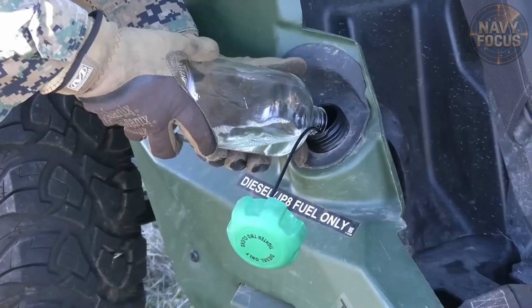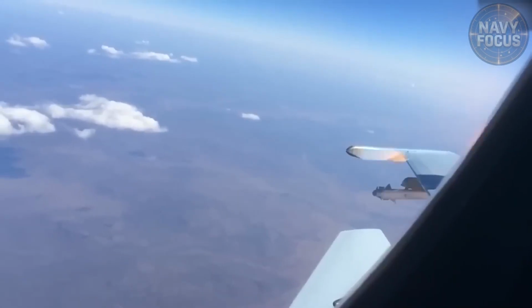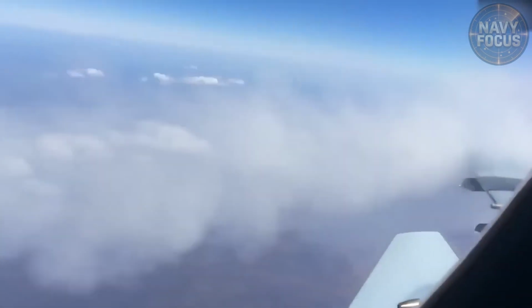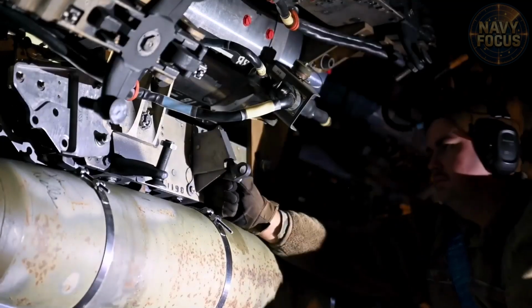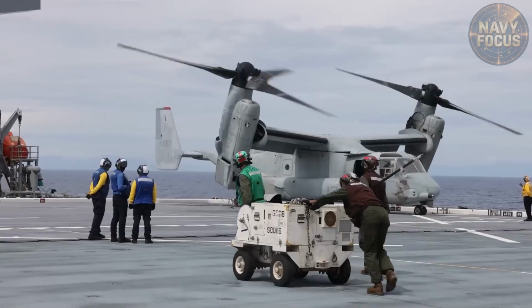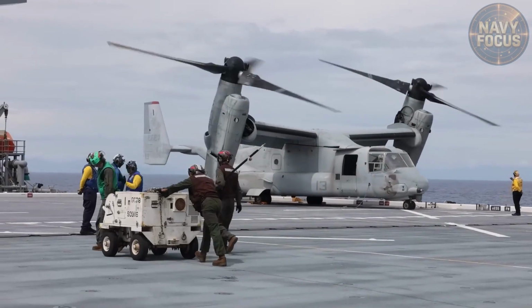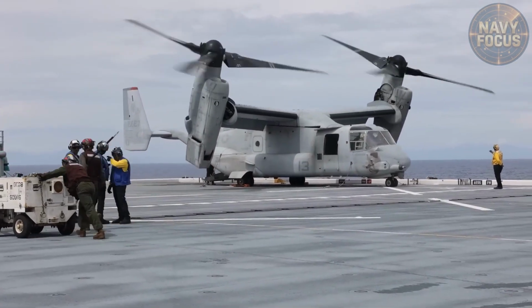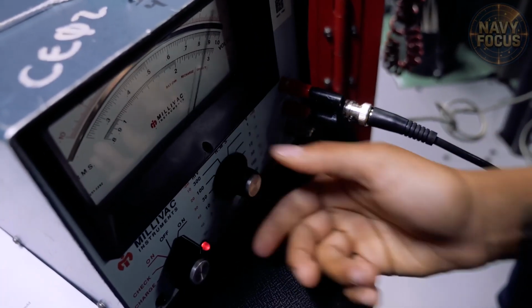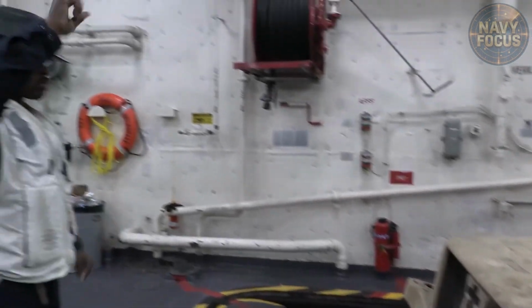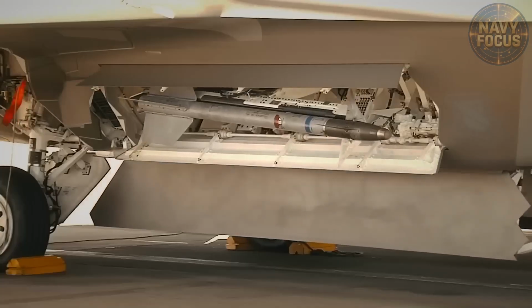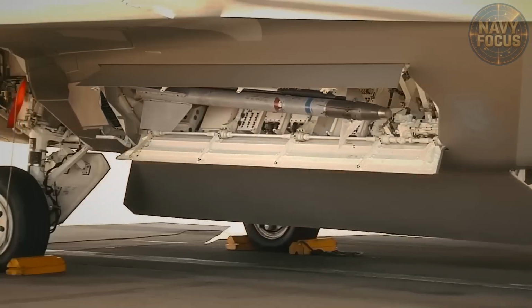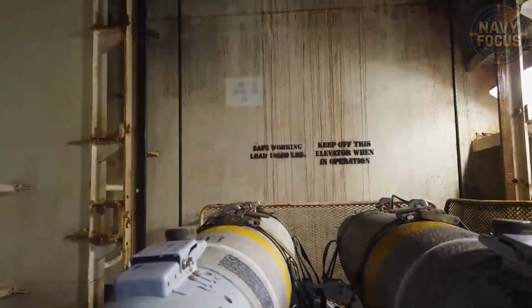He calls the generator room at 3:41 a.m. While you wait for the heat packs, start the GTG3 air start preparation sequence on battery power. Position the air start valve, pre-stage the ignition, run the pre-start checks on battery power. When the filter is warm and the fuel is flowing, I want to be ready to engage the starter immediately.